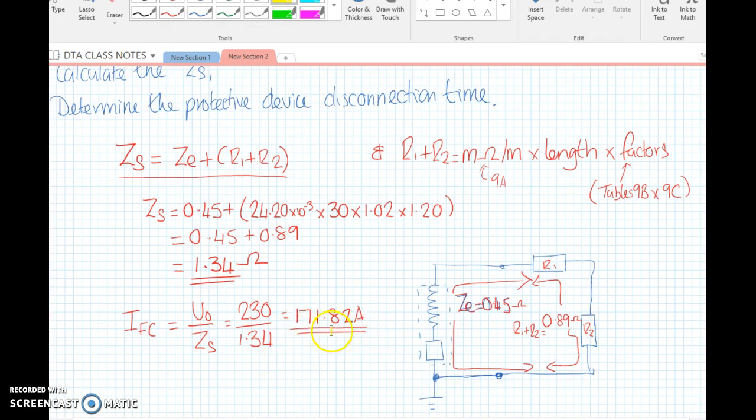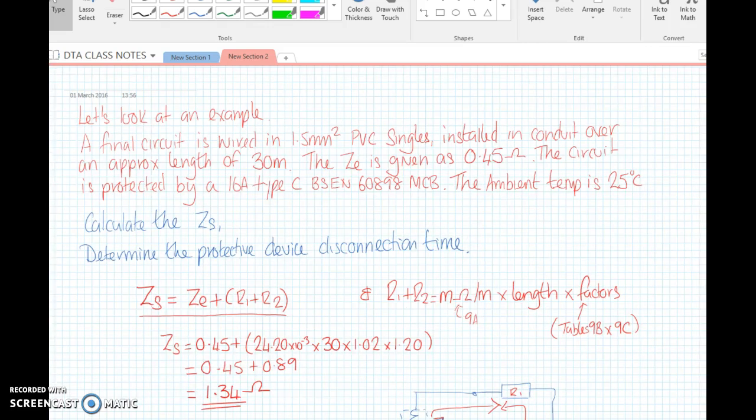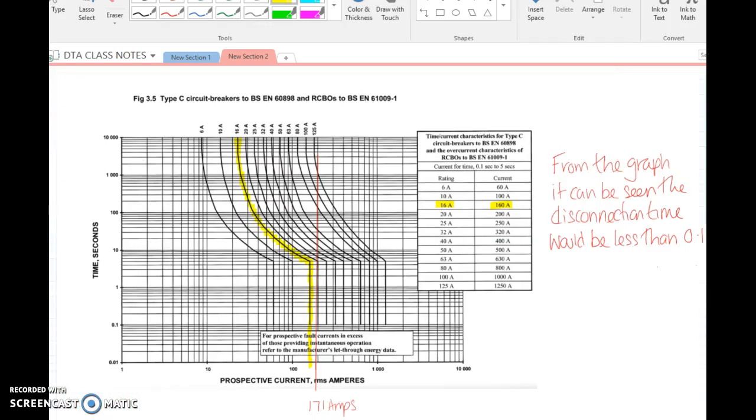That's our ZS 1.34, so now we need to work out our fault current. I've done a sketch of our circuit: we have a ZE of 0.45 which we're given, and our R1 R2 is 0.89 that runs through here. The next thing to look at is the actual protective device. The brief tells us it's a 16 amp type C 60898, so I've gone through our regulations and found this table.